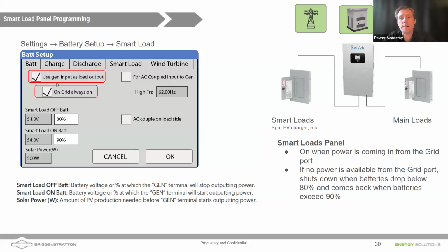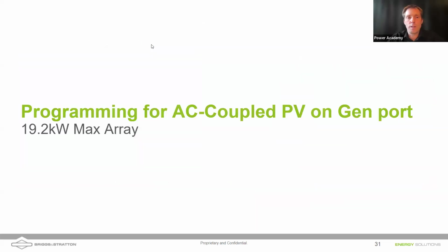It'll keep that sub panel always energized as long as grid power is there, or something coming from grid power, like maybe a generator for an off-grid system. And then the next values that we can see is we can turn off the smart load output if the battery drops below 80%. You can set that to whatever you want it to be. You might want to keep your car charger on until your home battery is discharged to 60%. So you could set this at 60%. The value for load back on is if we've actually hit that low value and the load's output is turned off for smart loads, we're going to wait until those batteries charge back up above 90% to turn it back on. That way we don't get fluctuations of on, off, as loads and power is flowing. But essentially, this is a nice use and very easy to program a smart load output here into the Sol-Ark.